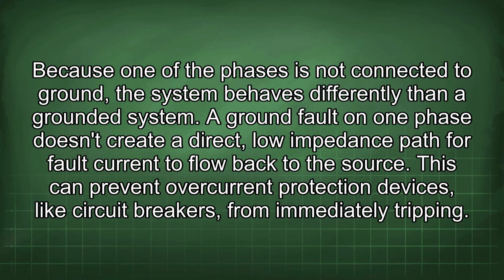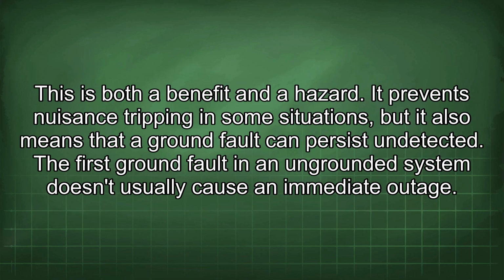A ground fault on one phase doesn't create a direct, low-impedance path for fault current to flow back to the source. This can prevent overcurrent protection devices, like circuit breakers, from immediately tripping. This is both a benefit and a hazard. It prevents nuisance tripping in some situations, but it also means that a ground fault can persist undetected. The first ground fault in an ungrounded system doesn't usually cause an immediate outage.